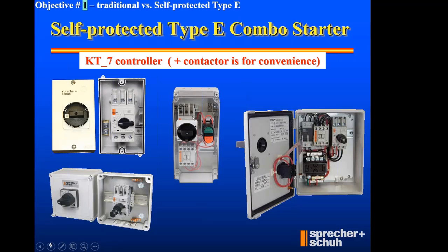So yeah, ultimately that is a combo starter, and we'll discuss how that achieves. But yeah, that device by itself is a manual combo starter. In the middle, okay, here now we've added a contactor to the bottom side of the controller. Up at the top, I'm saying, okay, KT7 controller does indeed comply with self-protected Type E rules.